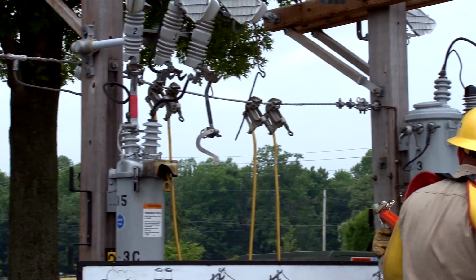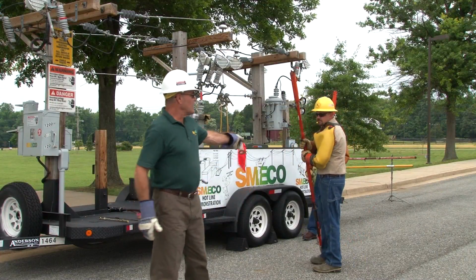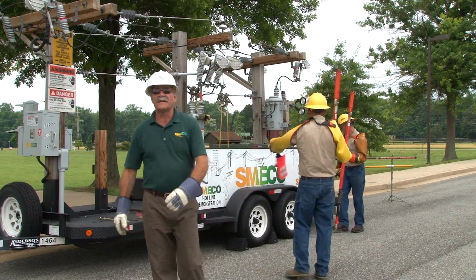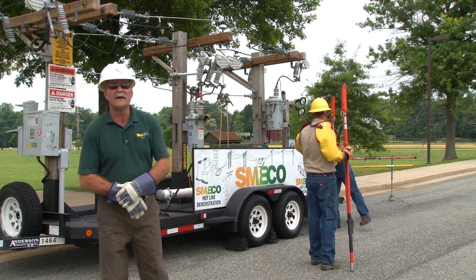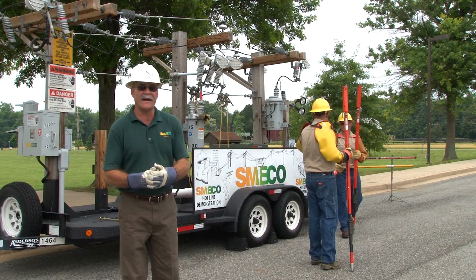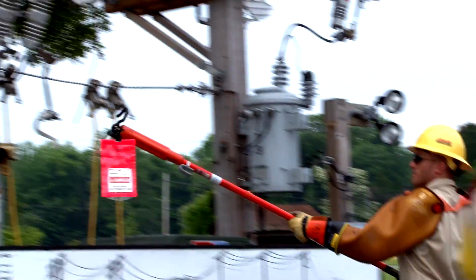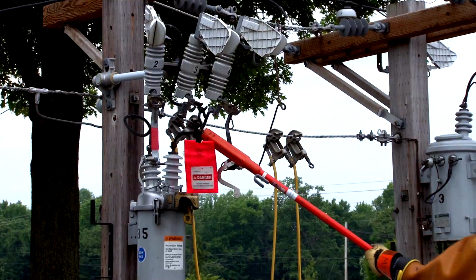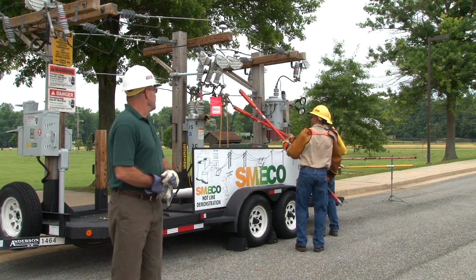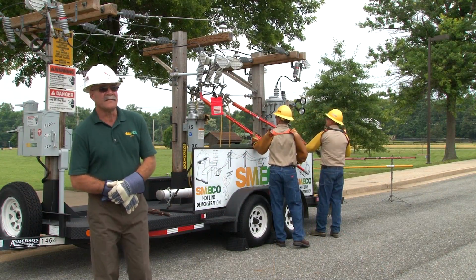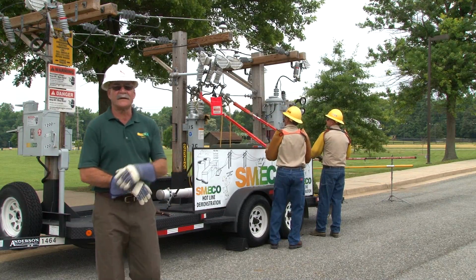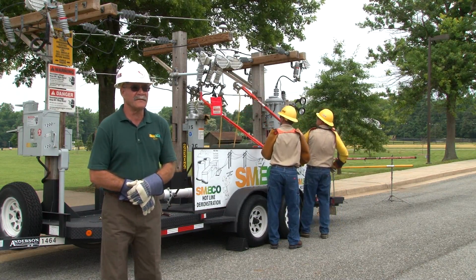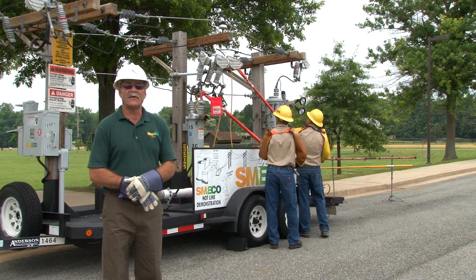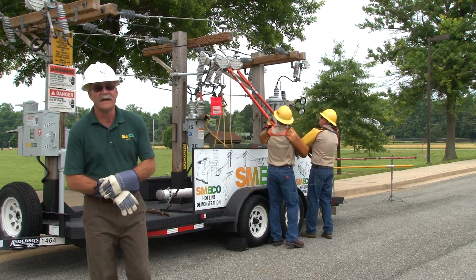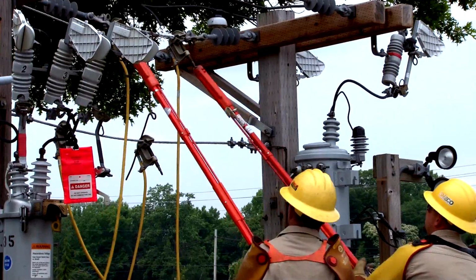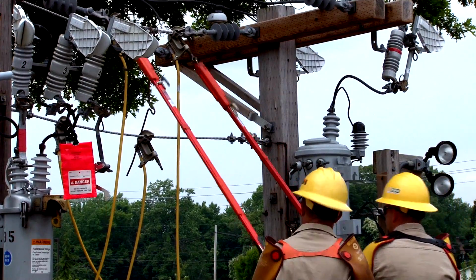They will install a caution tag, which tells everybody else that this line is being worked on to leave it alone. Either go down and help them, but never re-energize. The other procedure they do is put a ground on both sides of the area they're working in. This ground is installed for two reasons. One is personal protection from any incidental re-energizing of this line. The other, our most concern, is backfeed from generators.